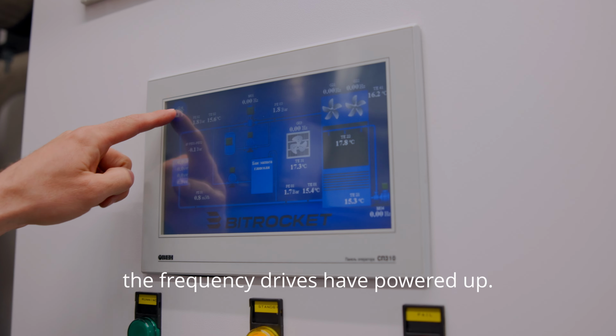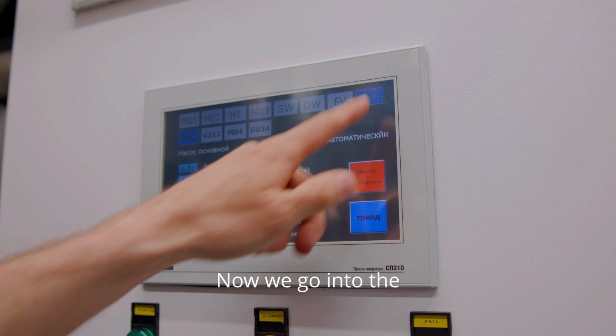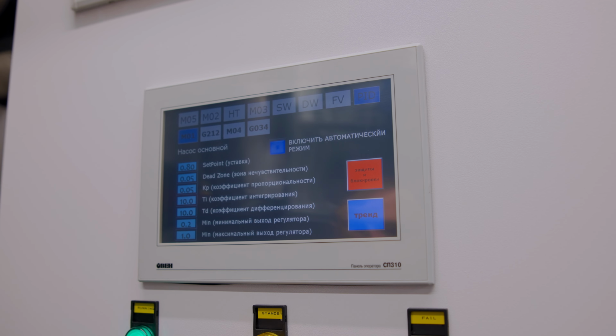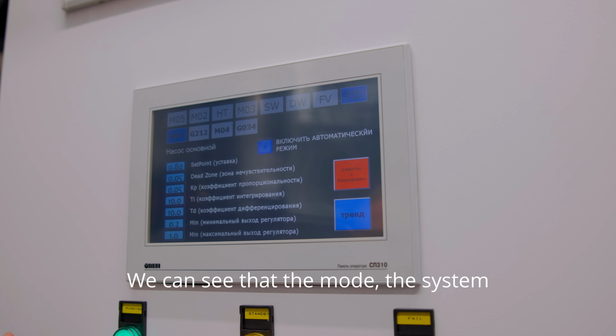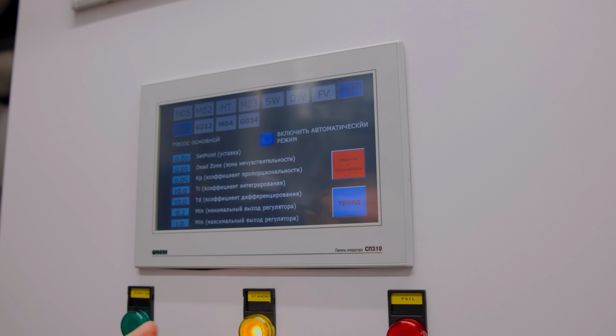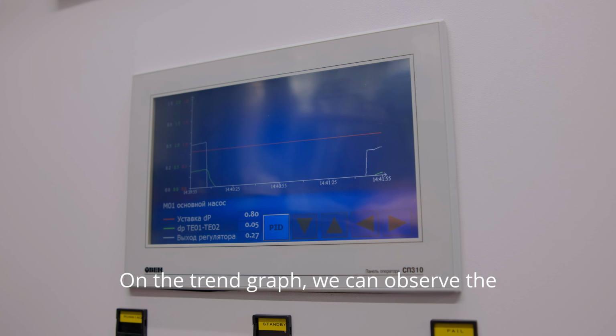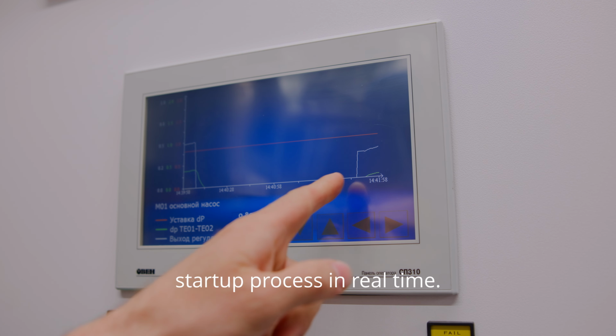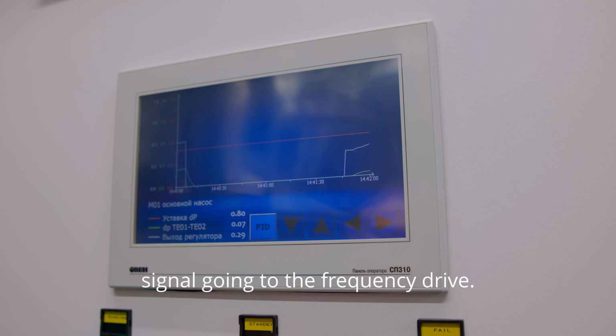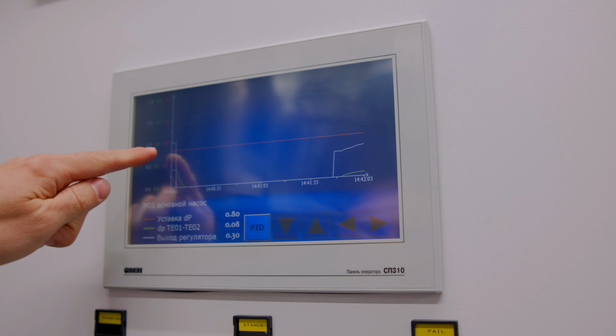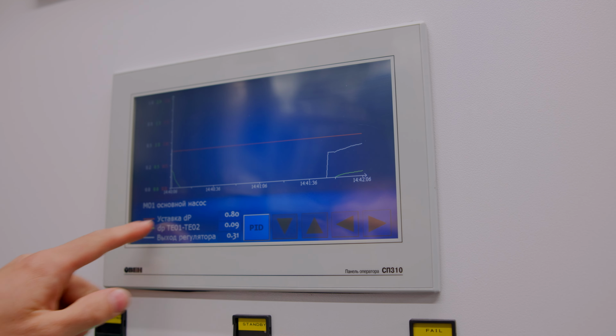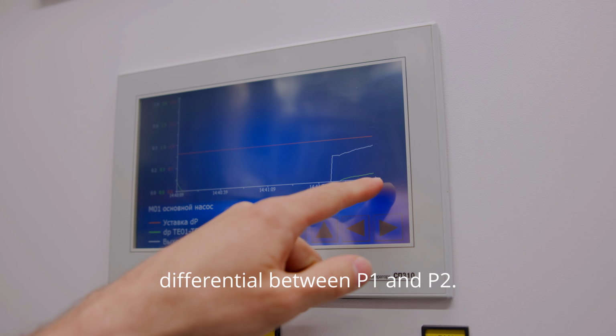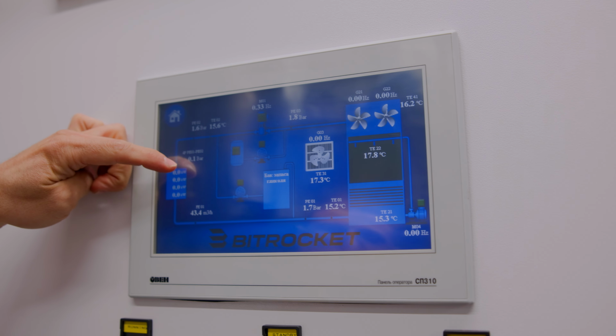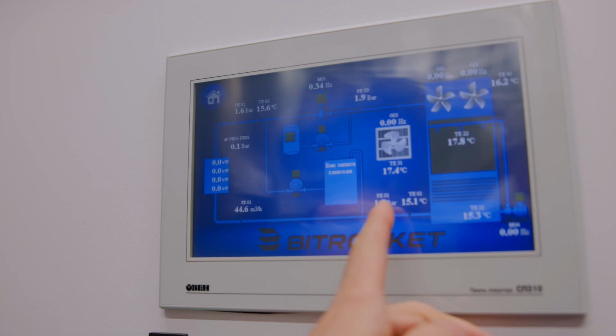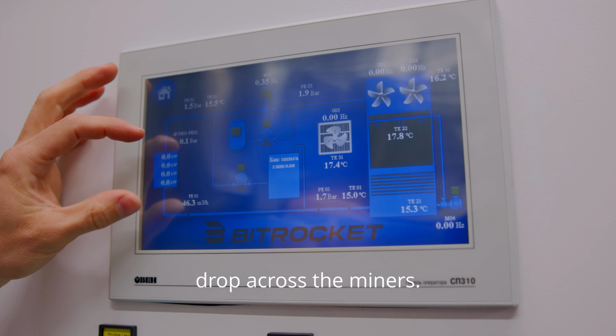The frequency drives have powered up. Now we go into the settings and start the main pump. We can see that the mode, the system state, has changed to starting. On the trend graph, we can observe the startup process in real time. The white line represents the current signal going to the frequency drive. The red line is the set point. The green line shows the pressure differential between P1 and P2. You can see how the differential is increasing. Now it's at 0.1 and rising. We are creating the required pressure drop across the miners.